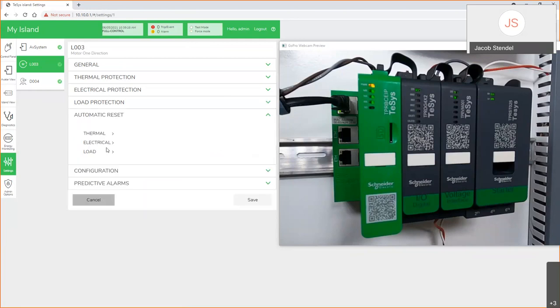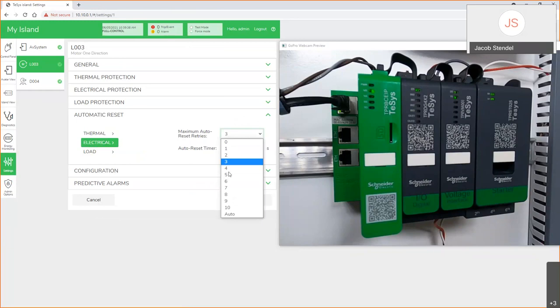Here's that automatic reset that I discussed. Thermal reset is when your motor overheats. You can have it wait a specific time and then try to start again. For electrical, I only want it to try 3 times. So it's configurable, and you can give it the reset timer that you want.